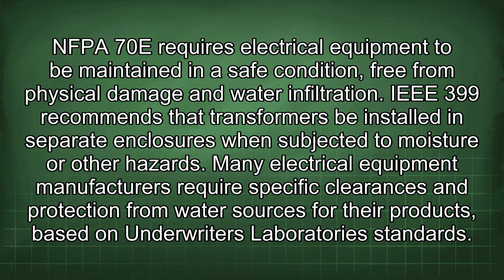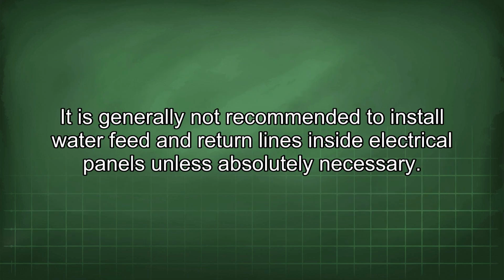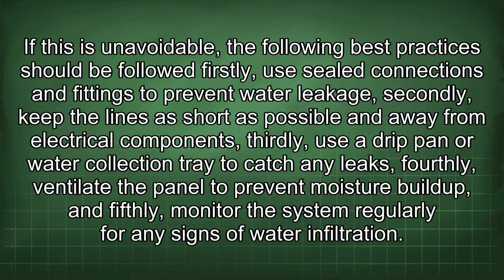IEEE 399 recommends that transformers be installed in separate enclosures when subjected to moisture or other hazards. Many electrical equipment manufacturers require specific clearances and protection from water sources for their products based on Underwriters Laboratories standards. It is generally not recommended to install water feed and return lines inside electrical panels unless absolutely necessary. If this is unavoidable, the following best practices should be followed.